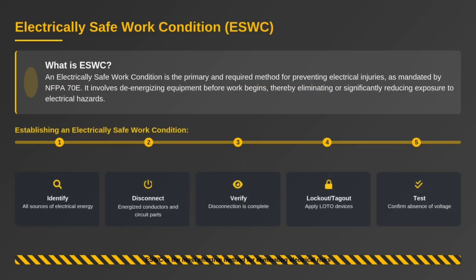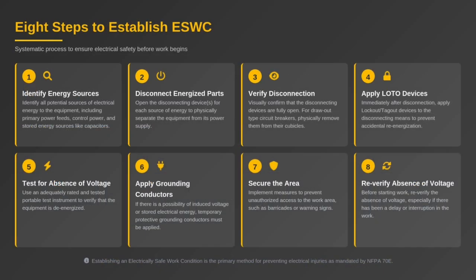The safest way to perform electrical work is under an electrically safe work condition, or ESWC. This means all energy sources have been identified, disconnected, locked out, and tested to confirm the absence of voltage. NFPA 70E requires ESWC whenever possible, as it completely eliminates exposure to electrical hazards. To establish an electrically safe work condition, follow these 8 steps.